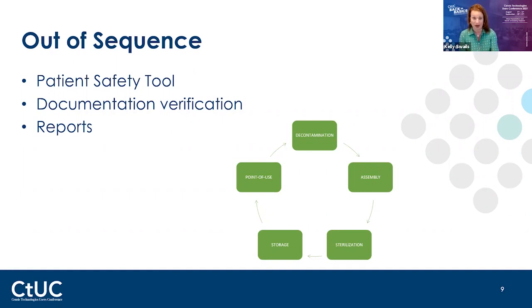Right there, I stopped some unintended consequences if those unsterile items were left in my department or made their way to a patient. Or maybe I look at this and think, well, I know I took it out of the sterilizer, I know it was sterilized. No, what that tells me is whoever created that load didn't scan it to the sterilizer, so they didn't count to make sure they match. And so there's no documentation showing it was sterilized. And if you didn't document it, it didn't happen. So then that needs to go back, go through the process and be sterilized.